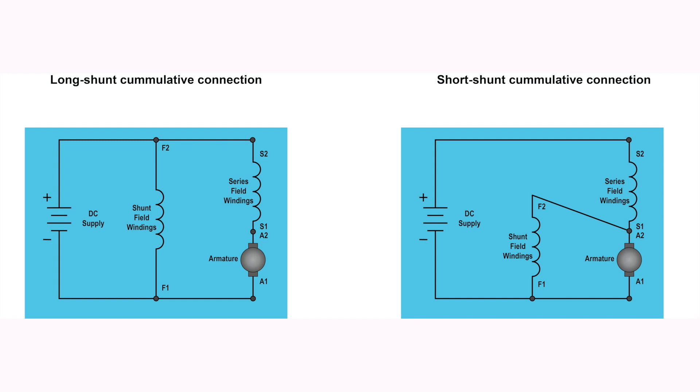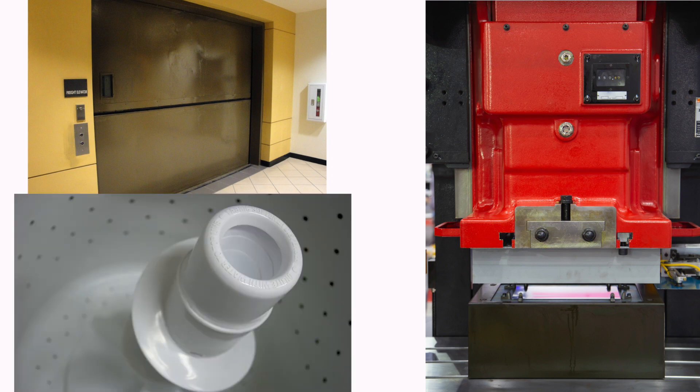For the short shunt compound DC motor, the shunt field winding is connected in parallel across only the armature winding and the Series field winding is connected to the supply current as shown. These types of motors can be found in applications such as freight elevators, stamping presses, agitator machines, and much more.